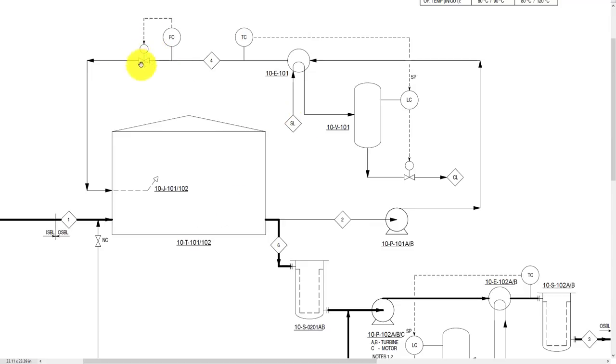You can see that there are two control valves shown in this loop. One will maintain the temperature by controlling the steam, and the second will maintain the flow. The symbol of the valve is a generic symbol of the remotely actuated valve. It can be hydraulic, pneumatic, or motor operated type.